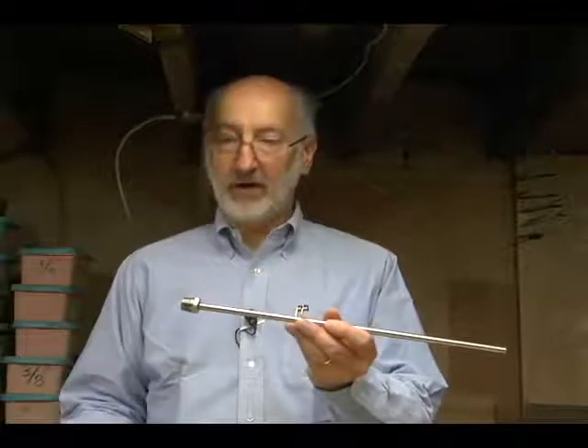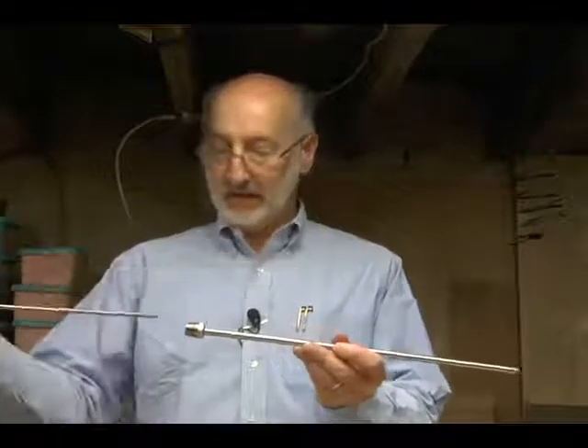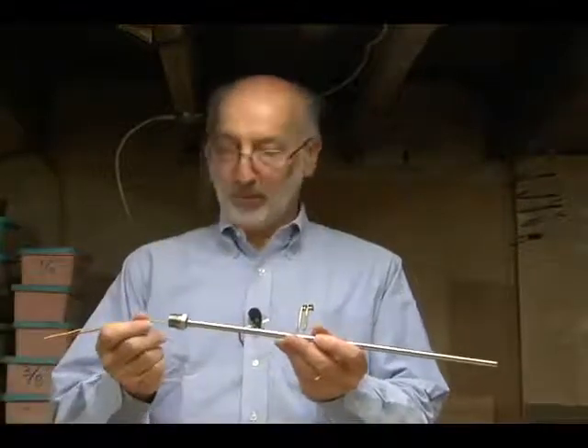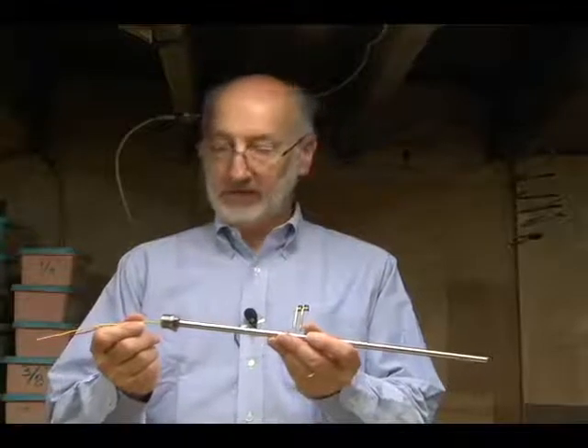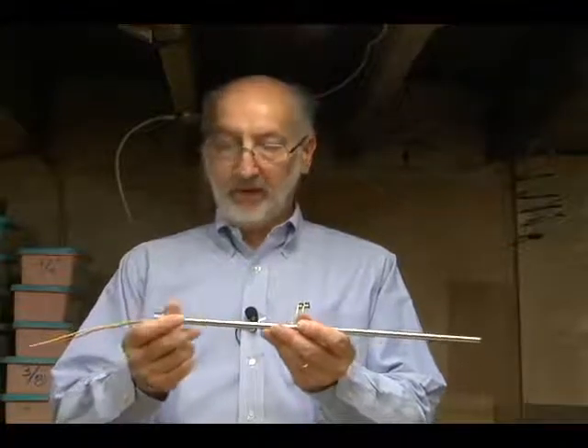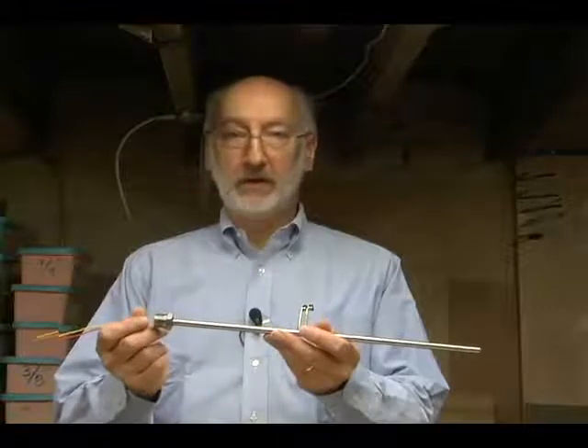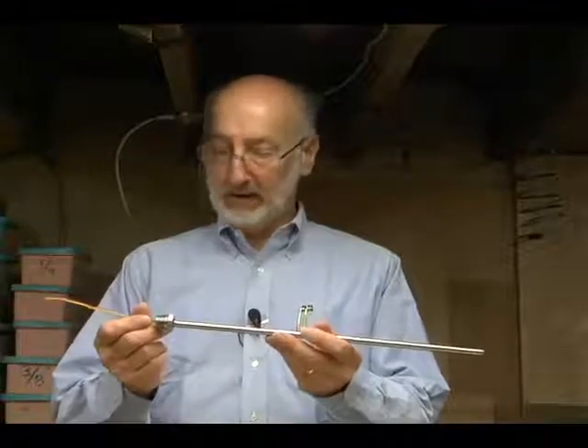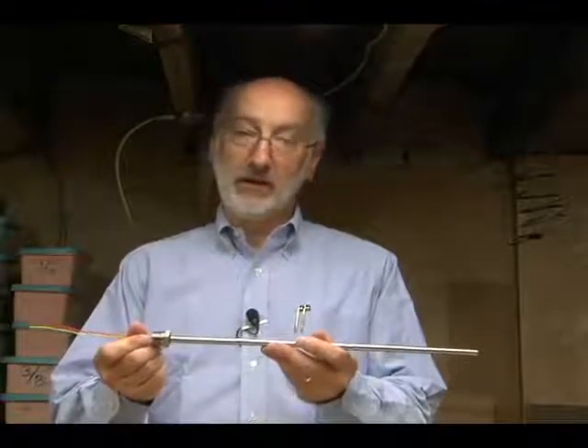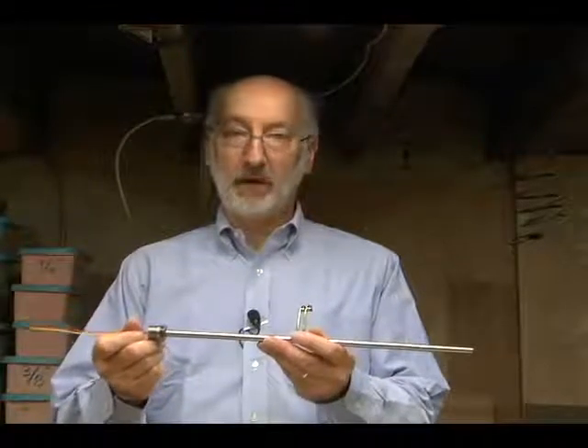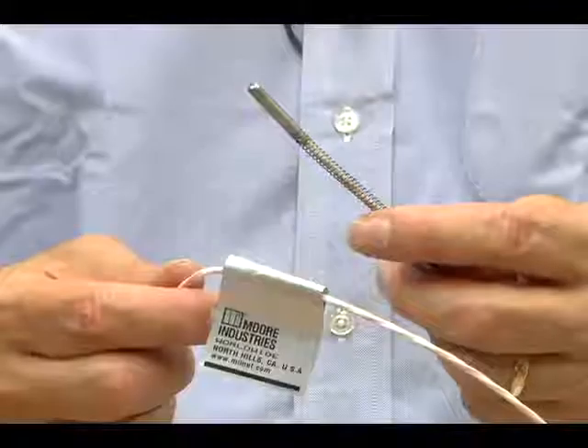Getting a fast response time requires that the sensor element is all the way down to the end of the thermal well and fills up the internal space as best as possible. If the thermal well is bent or if there's junk inside there, it's hard to push the element all the way in. If the element isn't all the way in, you'll get a temperature reading, but it may not reflect what you want from the process.